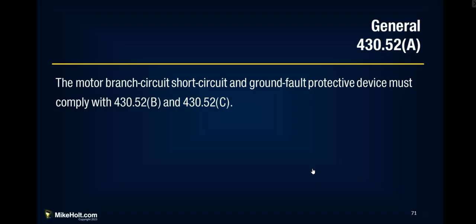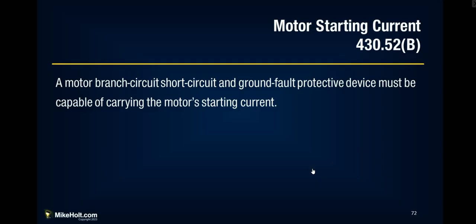My point being is this. If you look at it that way, the law of averages, if you're calculating this, you need to know that circuit type. They should be giving you in a test question the type of motor, and then you can nail that percentage. Once you've done that, and I'm sure we'll do a calculation here in a second, the motor branch circuit, short circuit, and ground fault protective device must be capable of carrying the motor's starting current. That is the issue with motors.